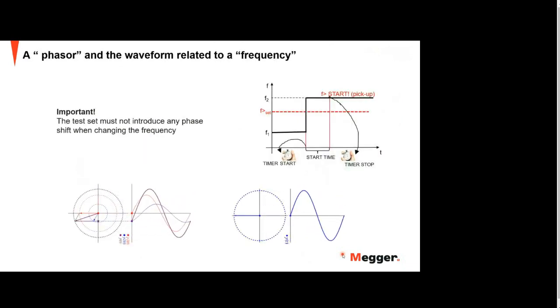One important thing when a relay test set is doing a change in the frequency, when you're simulating a change in the frequency, is that the relay test set shall not introduce a phase shift. Like here on this picture, we can see a simulation which is very common when testing over frequency protections. You have a pre-fault state and a fault state. You simulate, let's say, 50 hertz, and then you suddenly go to 53 hertz. And then you will see if the relay is reacting, and you're measuring the time.